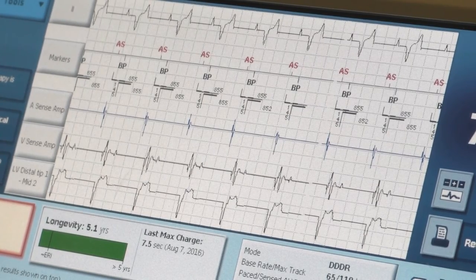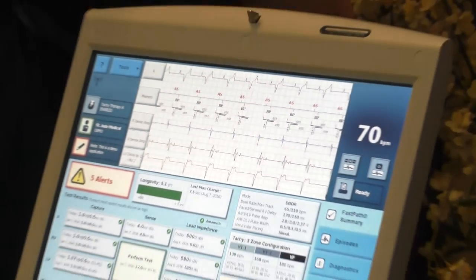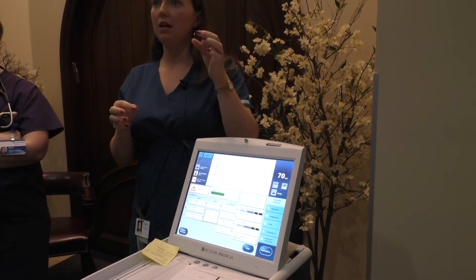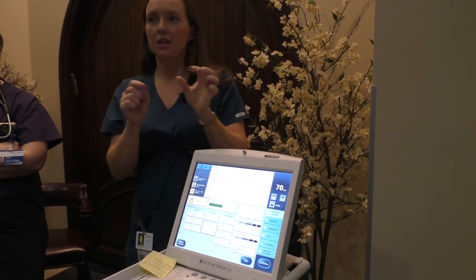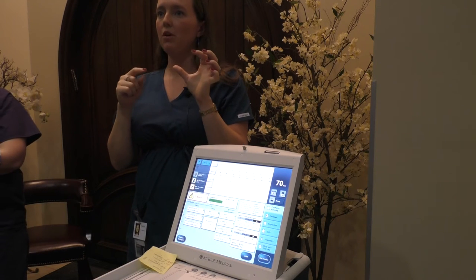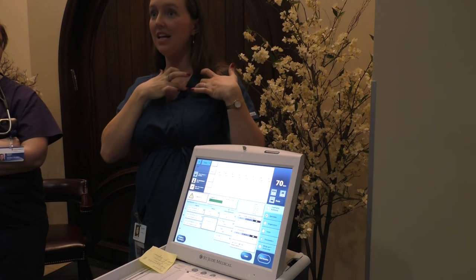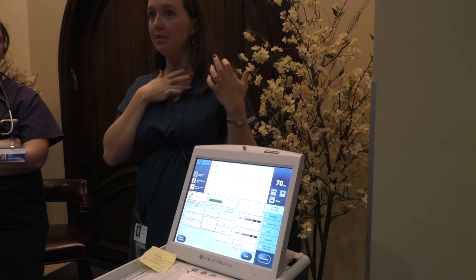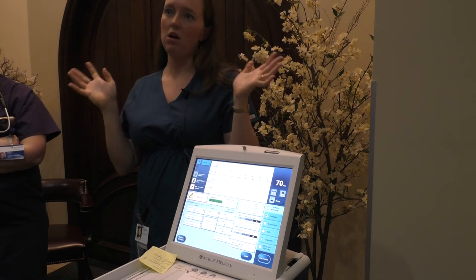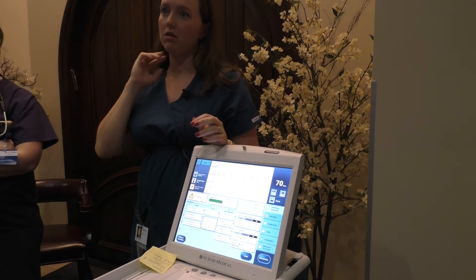The original pacemakers were unipolar — pacing from the tip of the lead to the can. I can still program current pacemakers that way. If there's a ring fracture or the short-spacing tip-to-ring stops working, I can reprogram to the can. The problem with unipolar pacing is the pacing vector is so large it can stimulate the pocket, causing pocket thumps. And with the large vector, you can oversense many things — valves, blood flow, atrial signal.